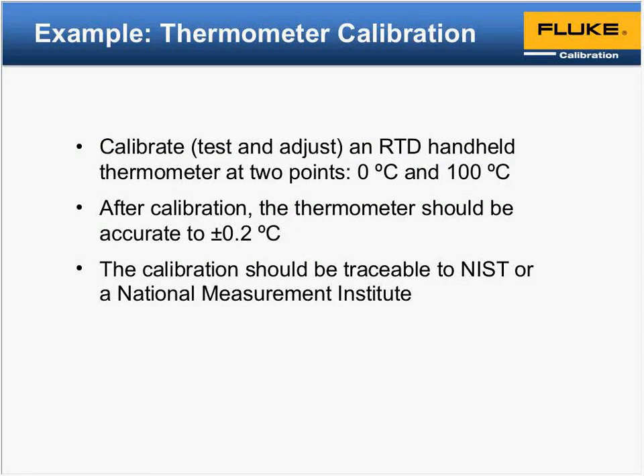All right. Example, we're basically going to run down a thermocalibration using the simulator. In this scenario, basically we're looking to calibrate, testing 2 points of an RTD handheld thermometer at 0 and 100 C. What we're looking to do here is, after the calibration, we'd like to get an accuracy of plus or minus 0.2 C with the system, and we're trying to get the unit to be traceable to NIST or National Measurement Institute. So those are the criteria that we're trying to accomplish in this scenario. So we'll just run through that, and then we'll go over what we may or may not have done properly.